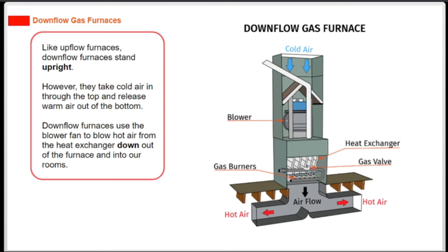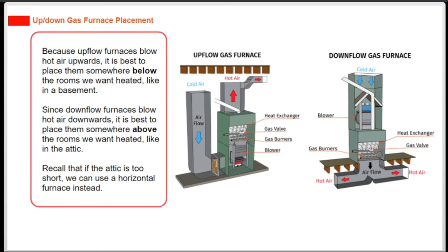Because upflow furnaces blow hot air upwards, it is best to place them somewhere below the rooms we want heated, like in a basement. Since downflow furnaces blow hot air downwards, it is best to place them somewhere above the rooms we want heated, like in the attic. Recall that if the attic is too short, we can use a horizontal furnace instead.